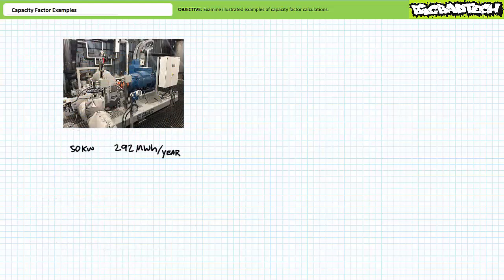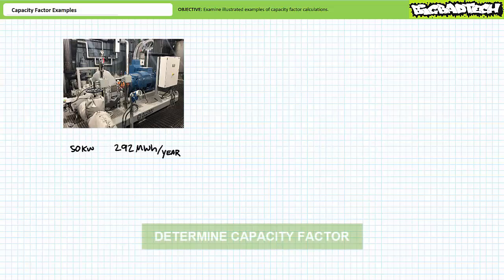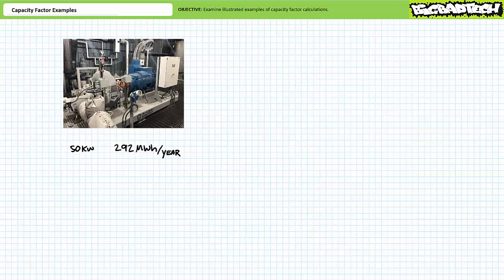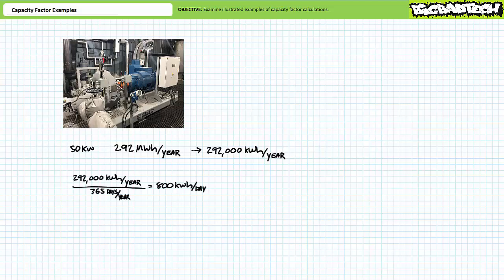Let's try another illustrated example. Consider a small 50 kilowatt steam-driven generator installed at a sawmill, known to produce 292 megawatt hours of energy in one year. See if you can determine the capacity factor of this generator — pause the lecture and try this on your own. If you're tracking, you should have obtained the following results. Let's first determine the average daily energy output of this steam-driven turbine in units of kilowatt hours. 292 megawatt hours is equivalent to 292,000 kilowatt hours. Dividing by 365 days per year gives an average daily energy output of 800 kilowatt hours.